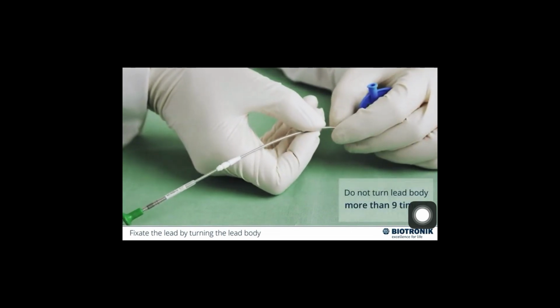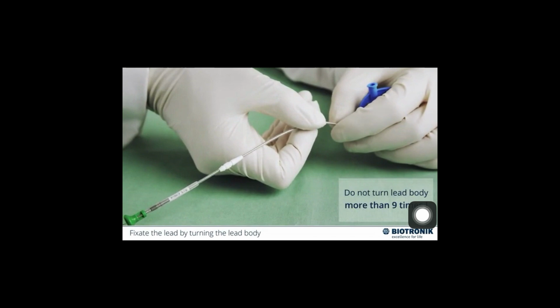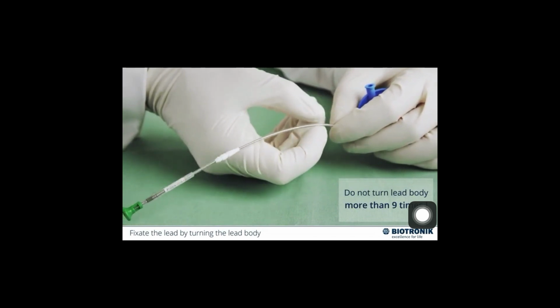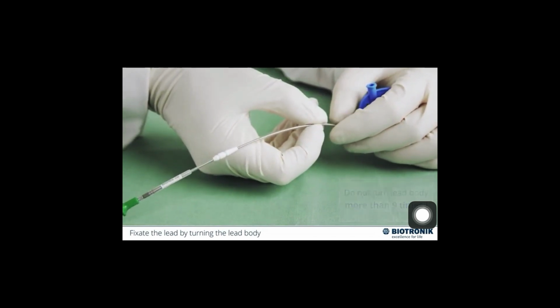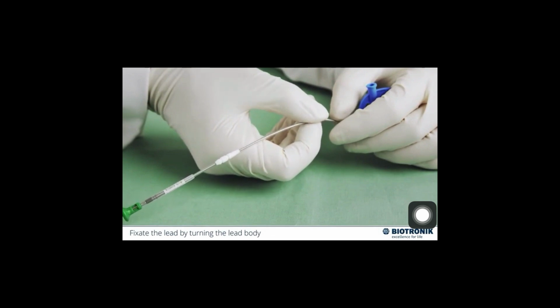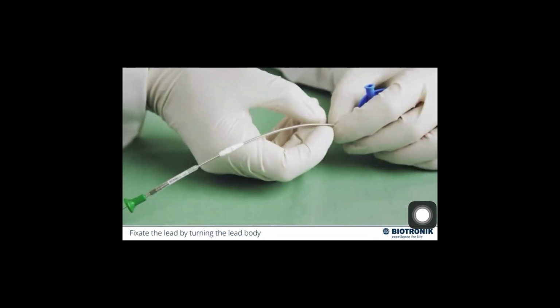Do not turn the lead body more than 9 times. This could damage the tissue or cause tissue to become trapped within the screw mechanism, which could then hamper and affect any future repositioning attempts. The number of turns needed to fixate the lead depends on several factors like lead lengths, the angle of the catheter and the lead tip, as well as the resistance of the tissue.